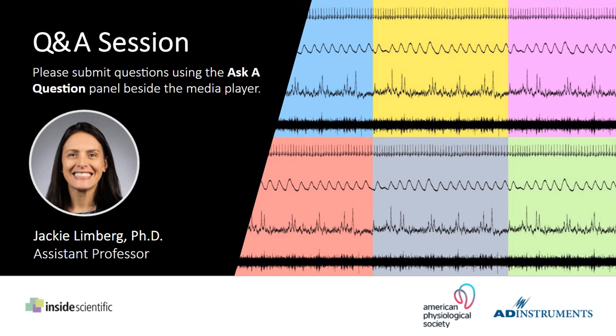So ADInstruments, I don't know how many years ago it was, essentially got access to the same algorithm. So if you use a Finapres, an independent device that's not associated with ADInstruments, it will give you an estimate of cardiac output, stroke volume, total peripheral resistance. And essentially, ADInstruments took that algorithm and created this NICO software. So it's very similar in that it will look at the pressure waveform of the finger cuff, which is what the other systems use, to get an estimate of stroke volume. And from there, you calculate with heart rate the cardiac output and the total peripheral resistance. So the technology is very similar. It's just built into the software.